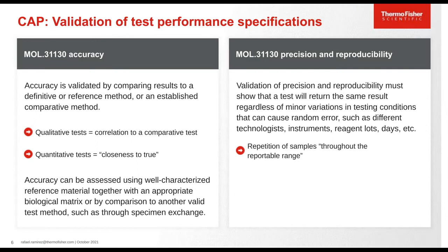Accuracy is validated by comparing results to a definitive or reference method or an established comparative method. For qualitative tests we look at correlation to a comparative test, whereas for quantitative tests we're looking for closeness to the true results. Accuracy can be assessed by using well-characterized samples in an appropriate biological matrix or by comparison to another valid test method such as a specimen exchange.